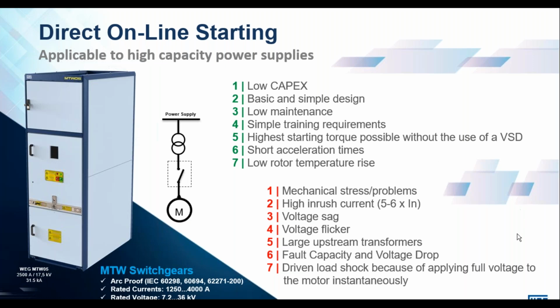Some disadvantages to direct online starting: mechanical stress is extremely high, especially on very large motors, the kind that we are talking about in this presentation. You get a very high inrush current, so the power supply network needs to be able to handle a high impact start. And then some other issues: voltage sag goes along with the high inrush current, voltage flicker, large power transformers needed if you've got a lot of large direct online loads starting, fault capacity, and driven load shock, which also talks to mechanical shock during direct online starting.